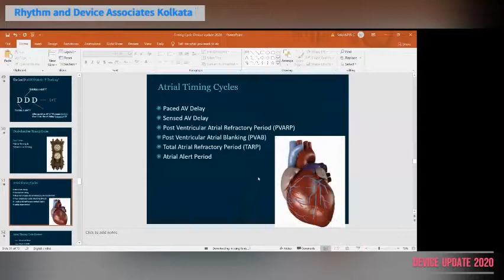So atrial timing cycles. In dual chambers, you have atrial timing cycles and ventricular timing cycles. What are the basic atrial timing cycles? Paced AV delay means the timing interval from the atrial pacing pulse to your ventricular event. You can program this as you want. What is a sensed AV delay? Sensed AV delay means the atrial lead picks up a sensed intrinsic P wave and triggers an AV delay at the end of which the ventricular lead delivers a spike. Along with this, we now have two refractory periods: the post-ventricular atrial refractory period and the post-ventricular atrial blanking. After every ventricular pacing, a refractory period and a blanking period are triggered.